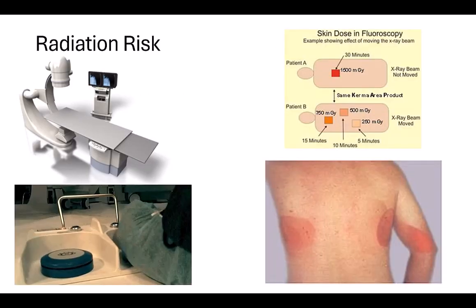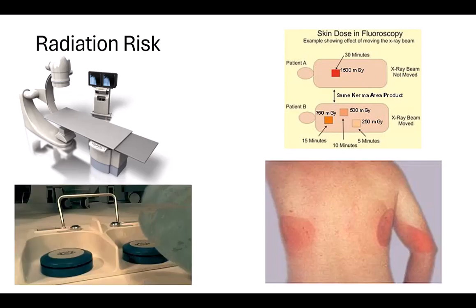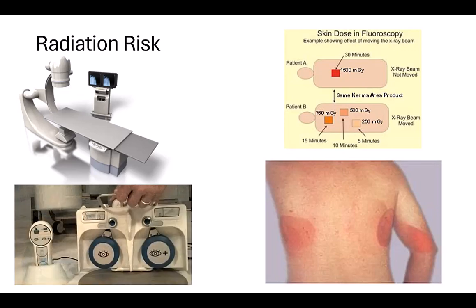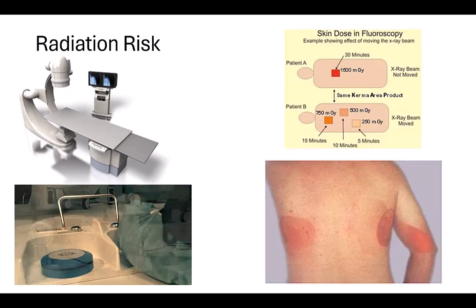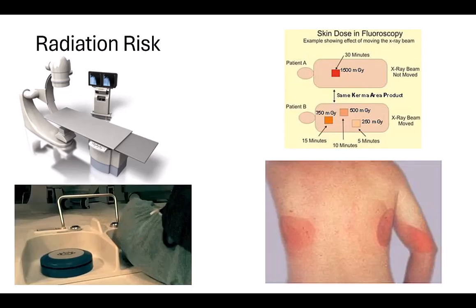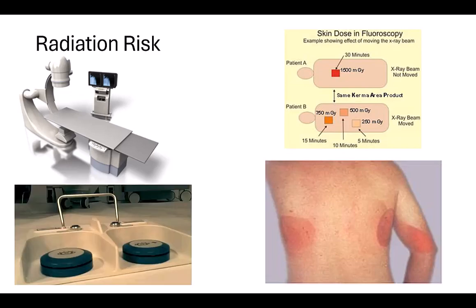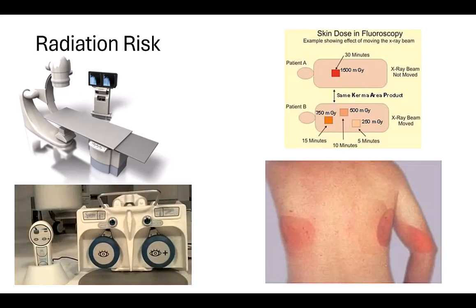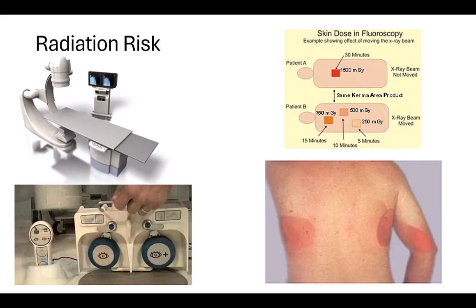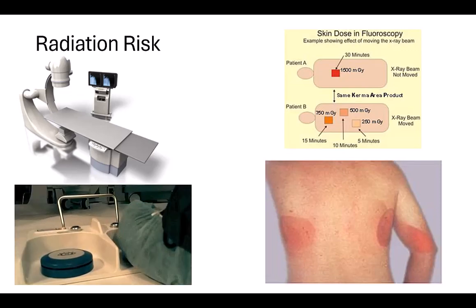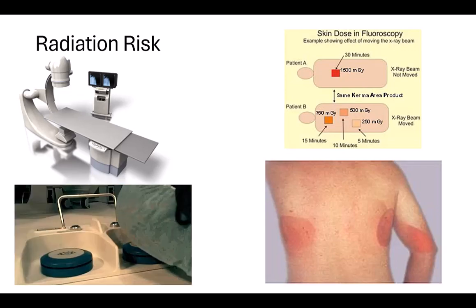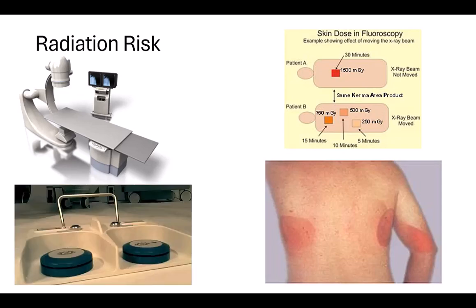Here we see a patient with post-procedure burns. Notice that we have a skin dose fluoroscopy graphic above the patient's images. We have patient A and patient B. On patient A, they had 30 minutes of continuous fluoroscopy and the beam was not moved. On patient B, they still had enough fluoroscopy, but by moving the beam to different areas, they've spread the doses to the areas being exposed. The difference is that the direct exposure is very low to different areas as you use multiple areas as compared with one heavy dose exposure, even though we're using the same amount of fluoroscopy.